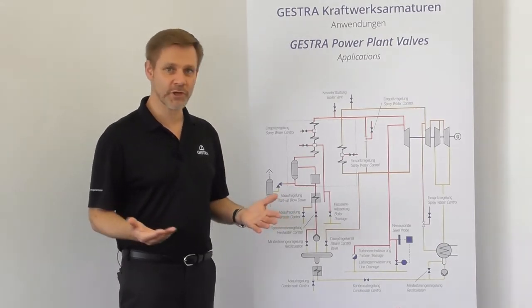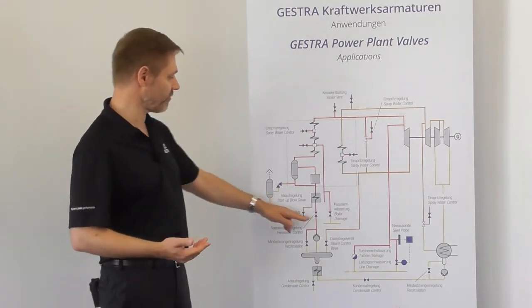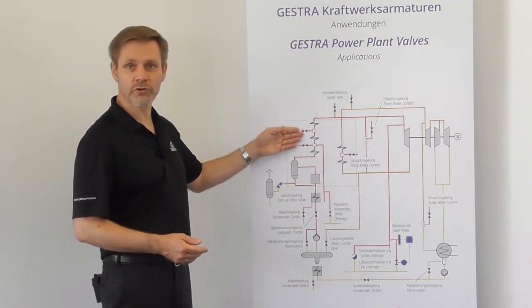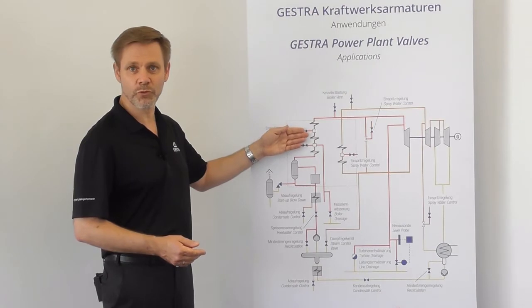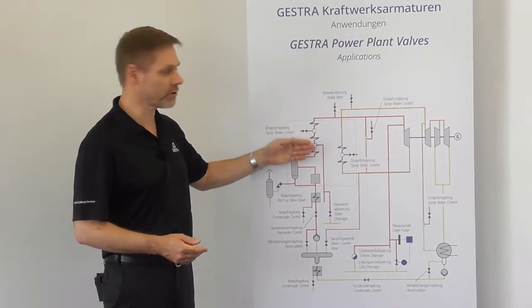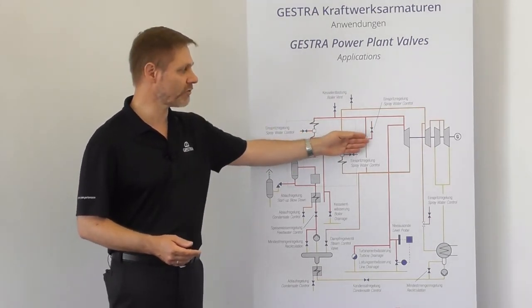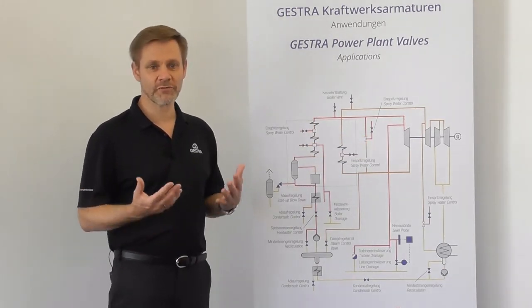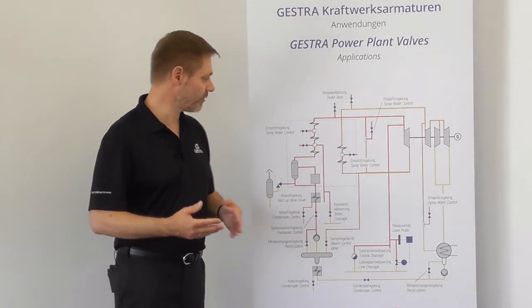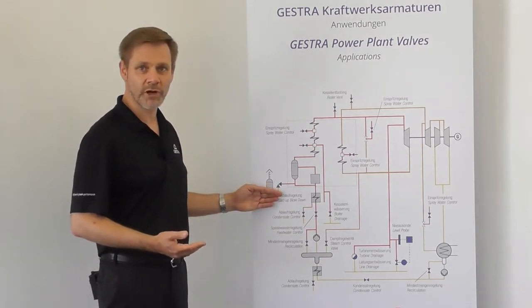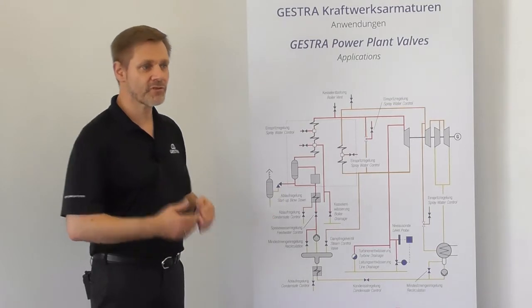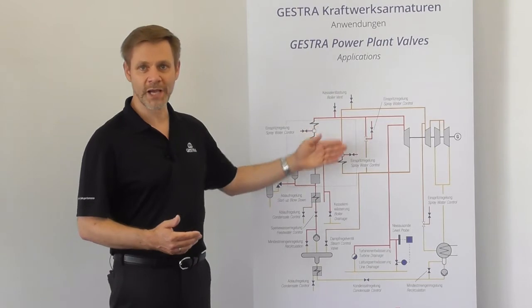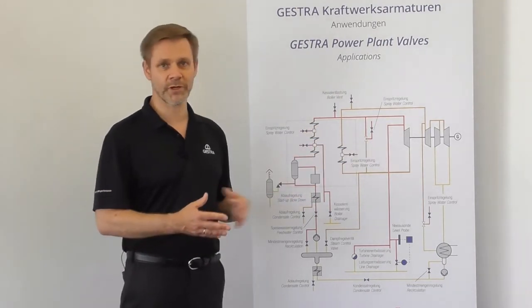An example for water applications are, for instance, the feed water control valve or the spray water control valves at the steam coolers between the super heaters or reheaters or at the bypass stations. An application for severe service at flashing water are, for instance, the start-up blowdown valves of the boiler drum, then all drain and warm-up valves for the boiler, for the piping system or for the turbine plant.